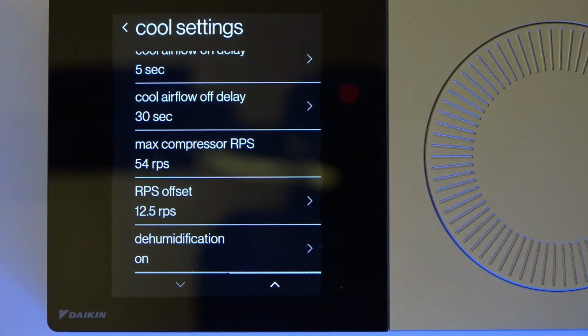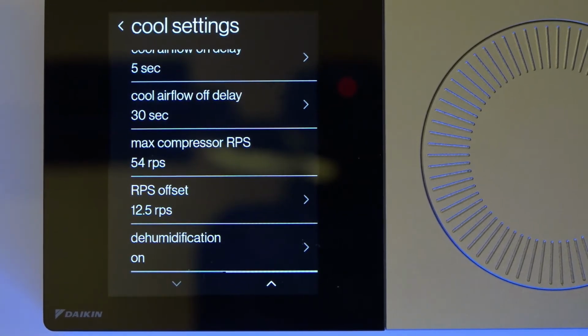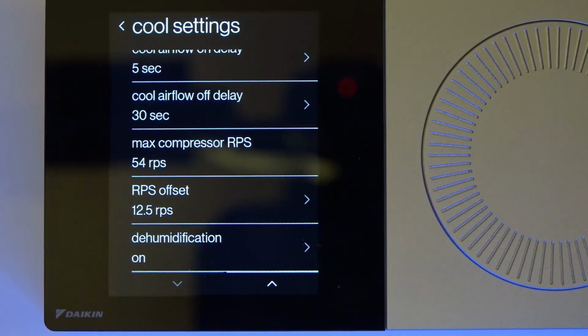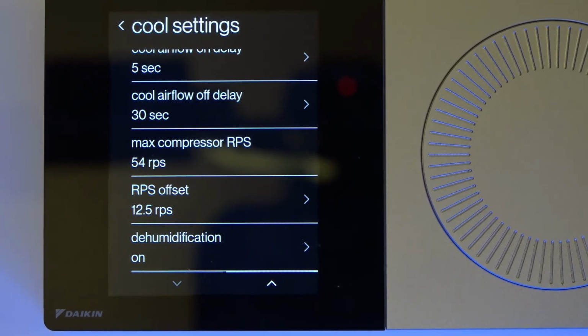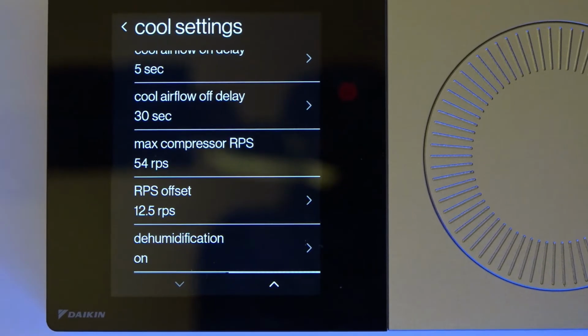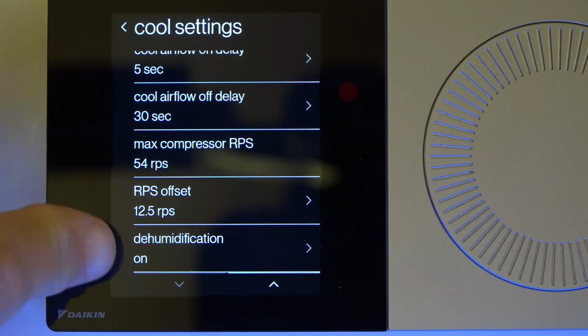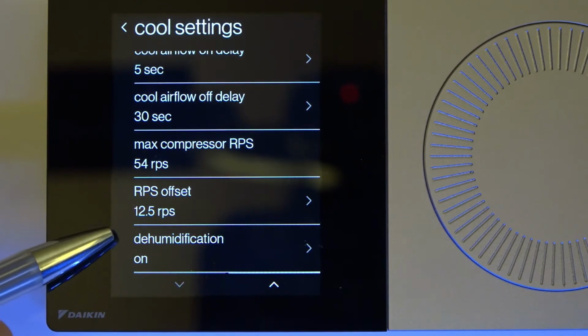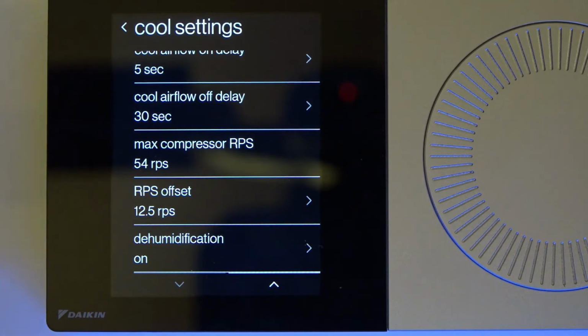These two areas here, I don't recommend tweaking it unless you talk to your local field service rep. Because there's going to be some things that we need to check before we start playing with the compressor revolutions per second. I do have some units that run at 111 revolutions per second. So if we start playing around with this, we increase the velocity of the refrigerant too fast, and you can run the risk of slugging a compressor. But all the way down here at the bottom, I want to make sure that my dehumidification feature has been turned on. In this case, it has.